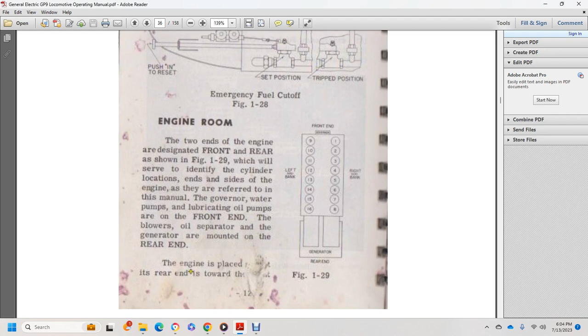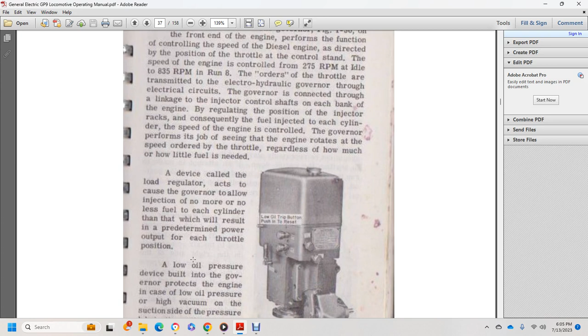133, engine governor. The engine governor, figure 1-30, on the front end of the engine performs the function of controlling the speed of the diesel engine, directed by the position of the throttle on the control stand. Engine speed control runs from 275 RPM to 835 RPM with the run 8 order of the throttle, transmitted through the electro hydraulic governor with the electrical circuit. The governor is connected through linkage to the injector control shaft on each bank of the engine, regulating the position of the injector rack and consequently the fuel injected into each cylinder. The governor performs the job of seeing that the engine rotates at the speed ordered by the throttle, regardless of how much or how little fuel is needed. A device called the load regulator acts on the generator to allow the injection of no more and no less fuel, which will result in the predetermined power for the input of the throttle.